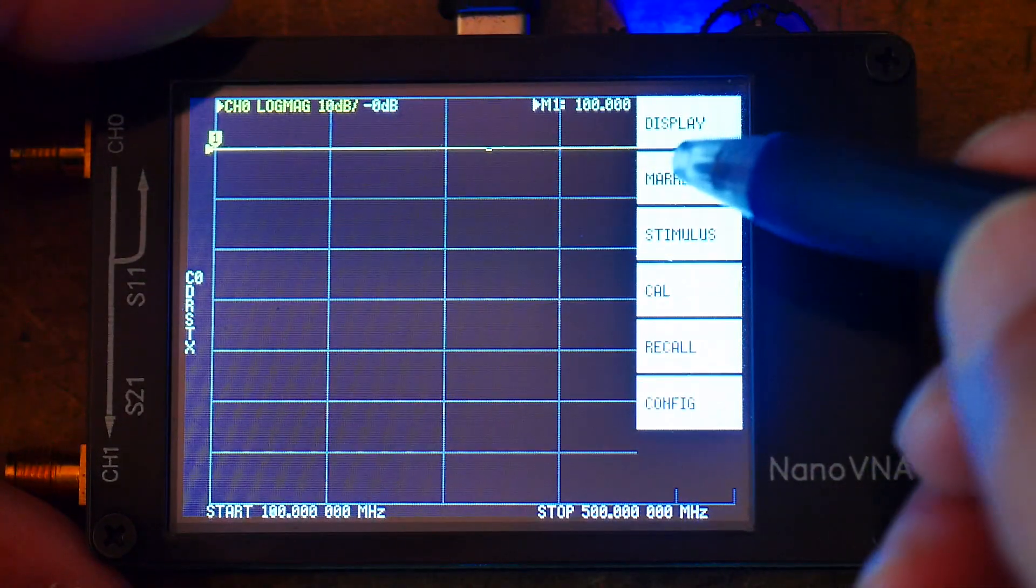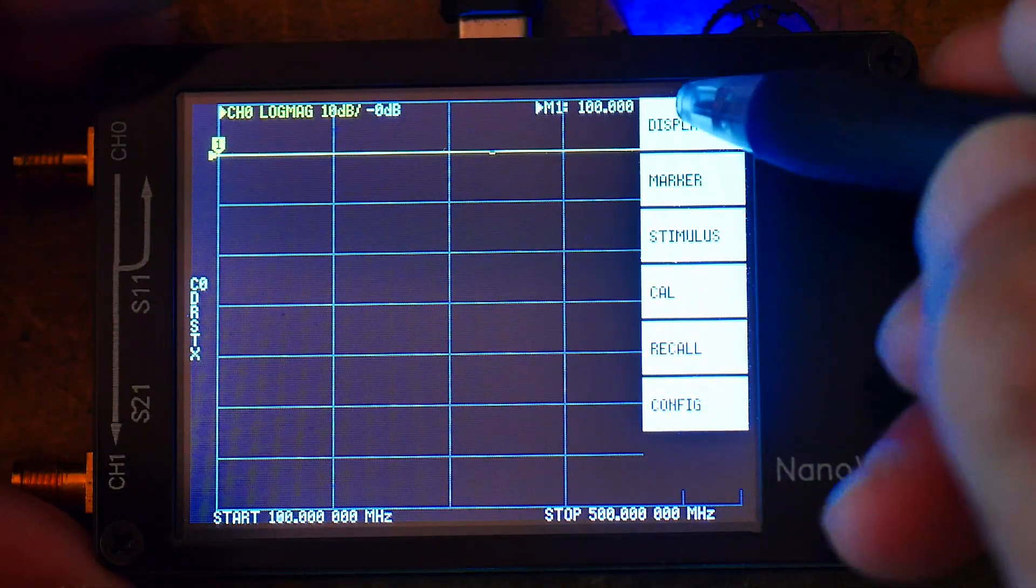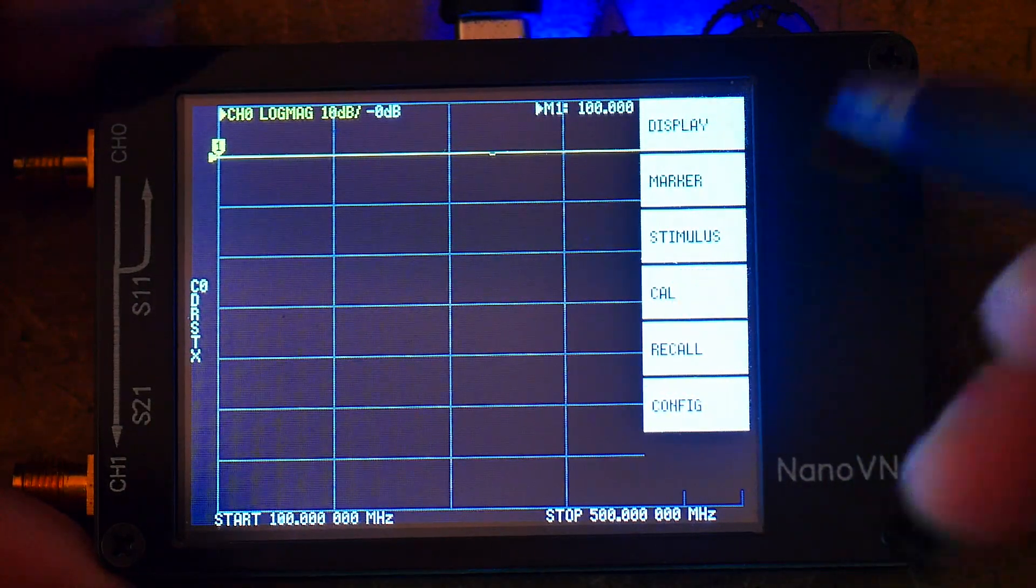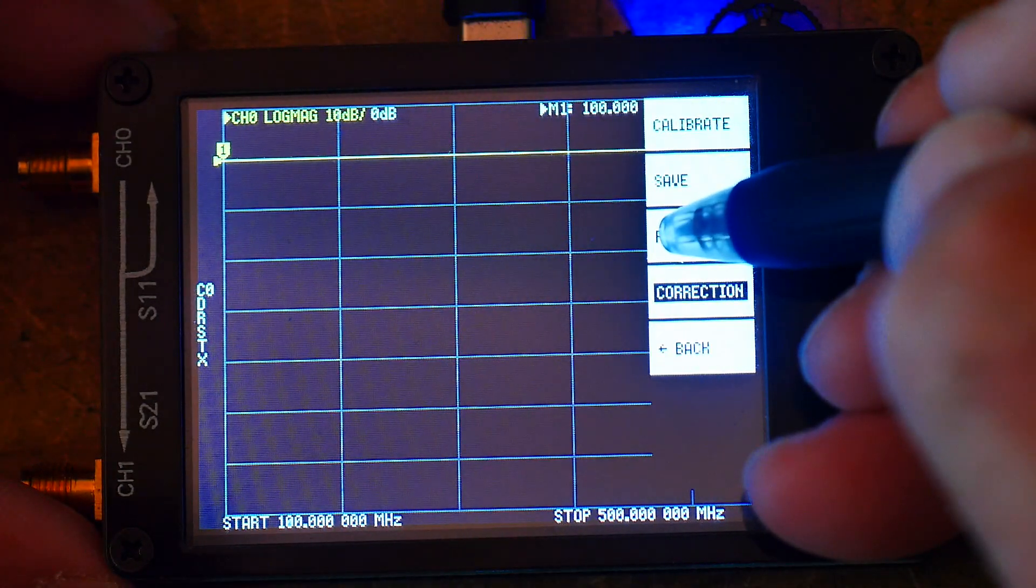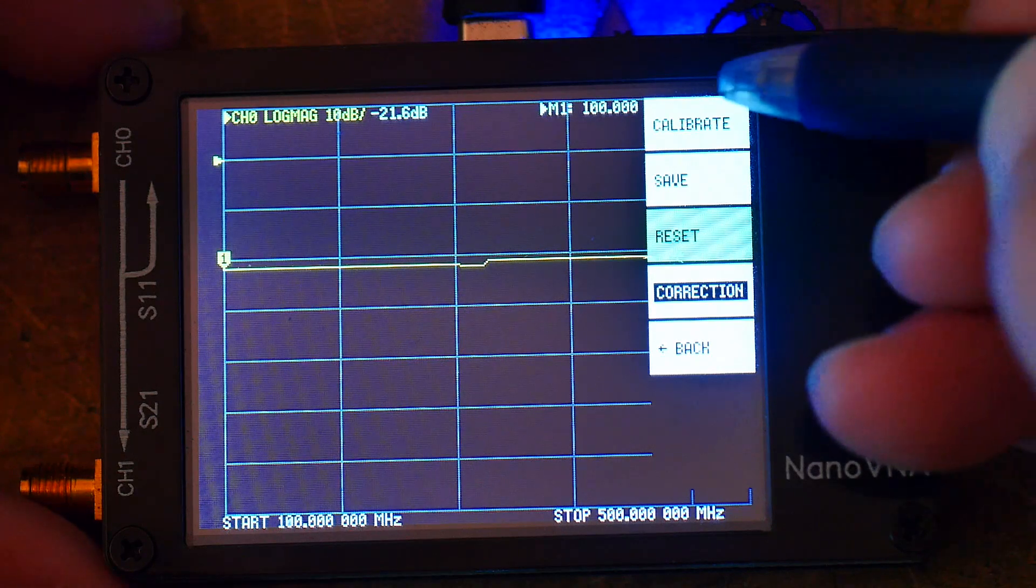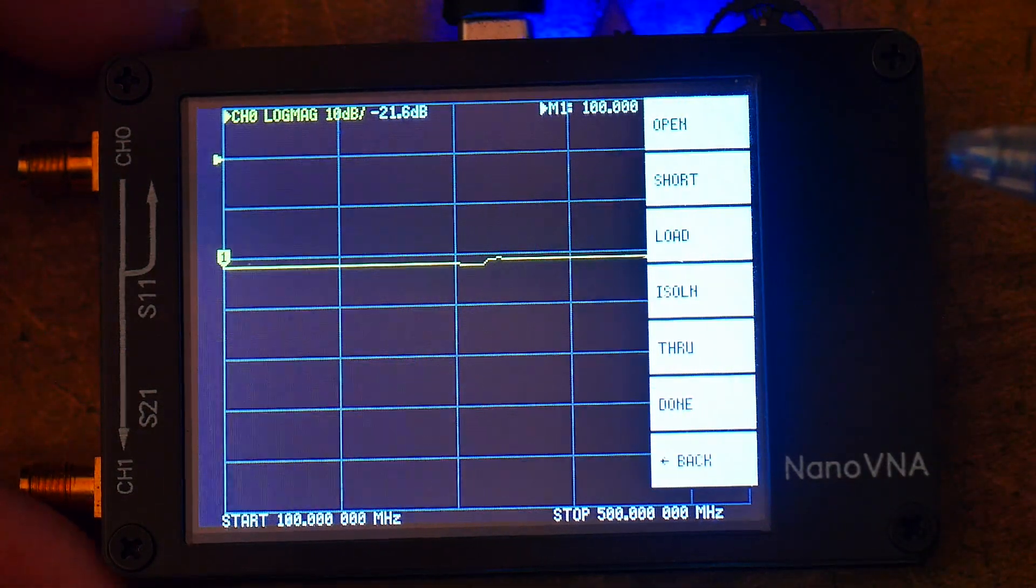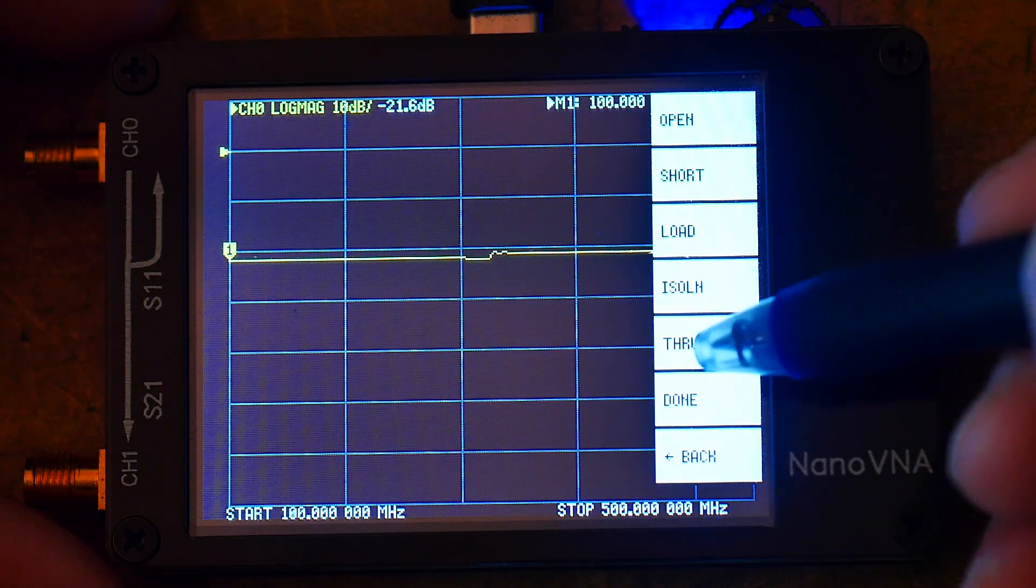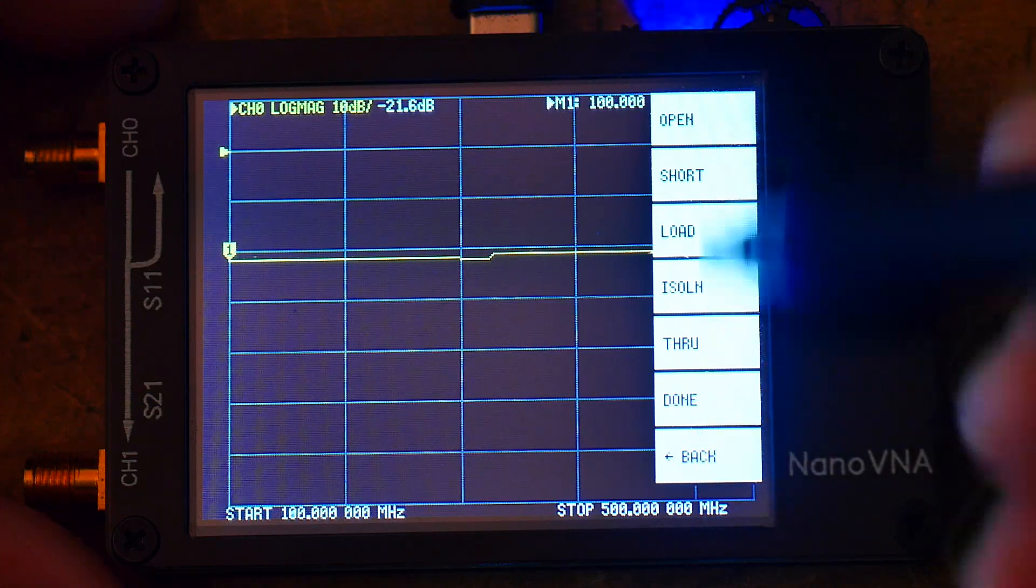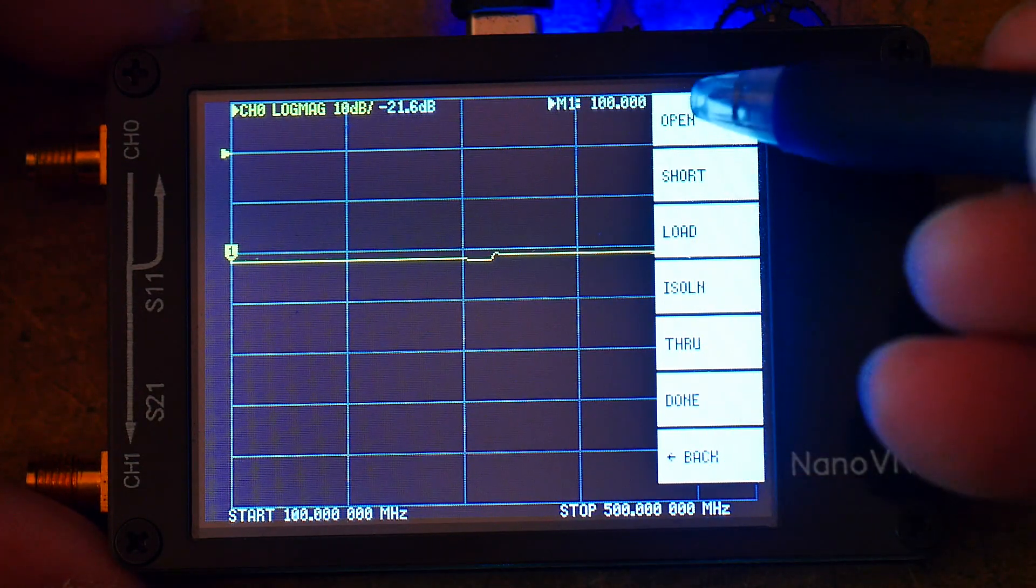The next thing we need to do is calibrate. So we're going to go to CAL calibrate. And I always hit reset. So click on reset. And now we go calibrate. And now we're in the calibrate menu. And now we'll see a list of things. Open, short, load, isolation, through, and done. And that's the order that you want to calibrate in. So you want to go from top down.